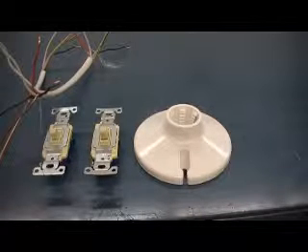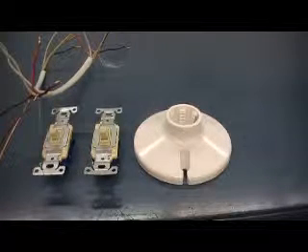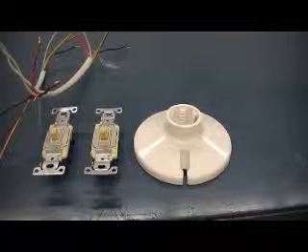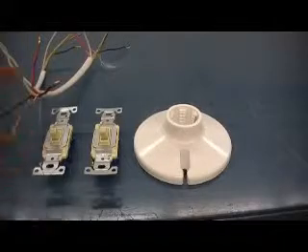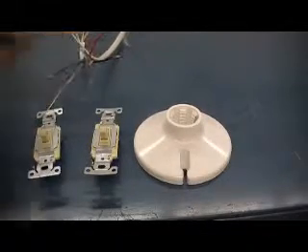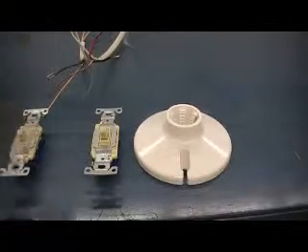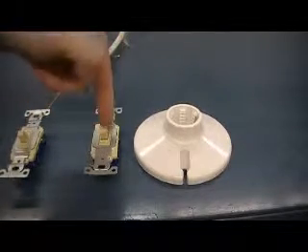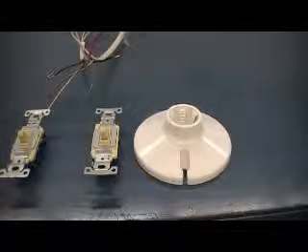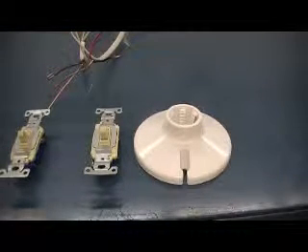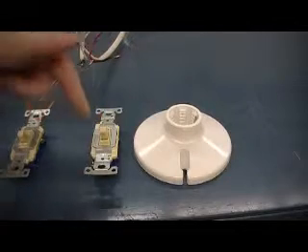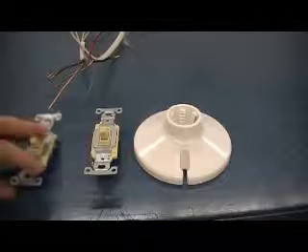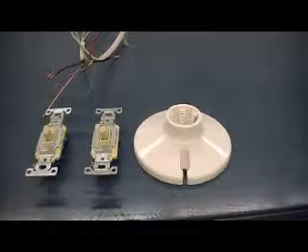So to sum up, you need two 14-2 wires and one 14-3. So coming in to the first switch, we have 14-2. Between the two switches is a 14-3, and then to the light is 14-2. Okay, so we need that 14-3 wire between here for our travelers. Okay, for the two hots to travel back and forth.